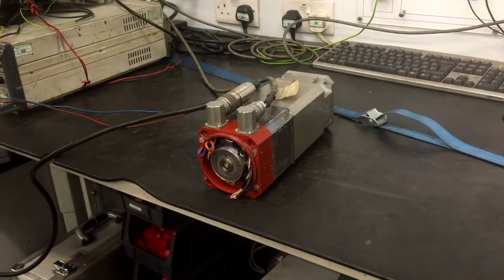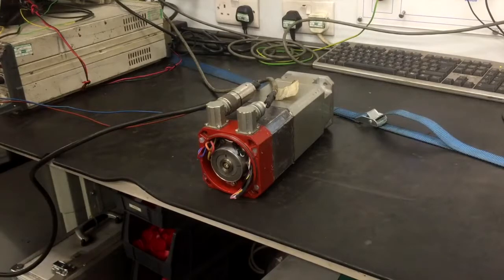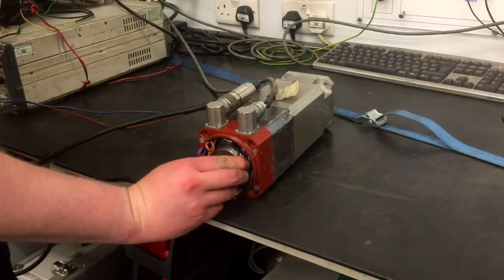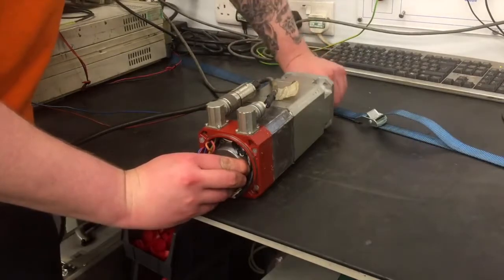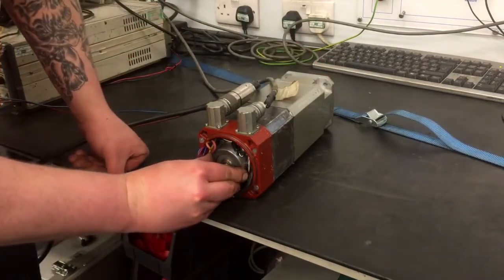As you can see, the Siemens servomotor has now been assembled. What we will do now is set the resolver alignment and the process that will follow to do this is to lock the rotor phases by applying a DC voltage between two of the phases and then moving the resolver stator until we get a zero degree position on our software.